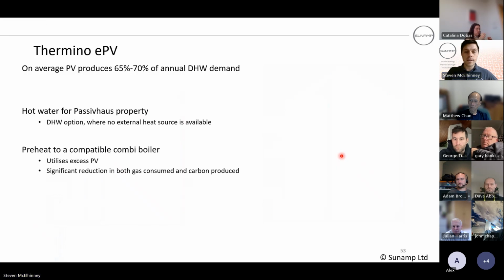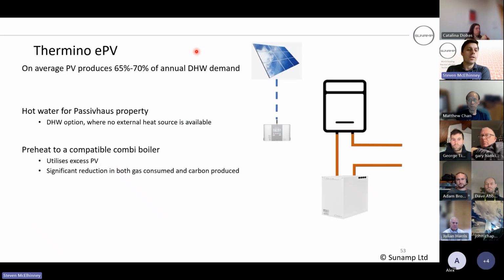So yeah, fit the blending valve as close as you can to the battery, blend it down, and then you've got less wastage of heat run through the house. So yeah, with PV, we reckon you can generate 65 to 70% of your annual hot water demand from PV alone. So the batteries will be good for passive house properties as well. There's no external heat source, so obviously PV on the roof, that's great. Preheat to a compatible combi boiler as well. So the idea being, the battery gets charged from your PV, comes out hot, runs through the boiler. The boiler doesn't fire up, and then you've got obviously hot water coming out of your taps.